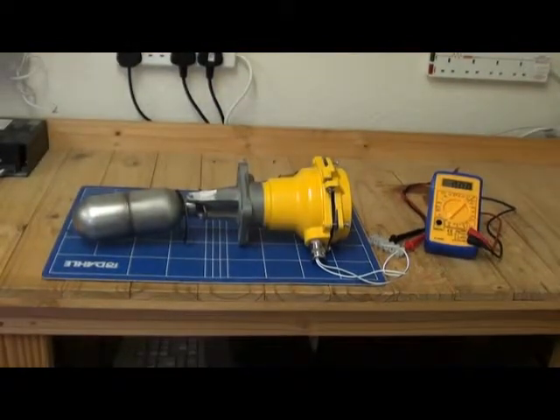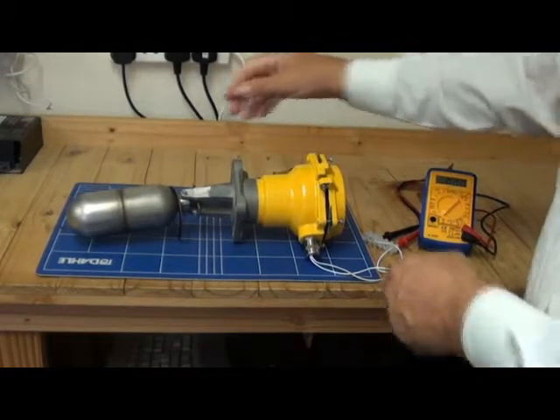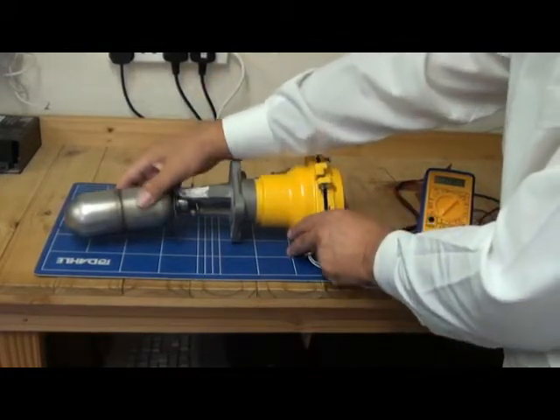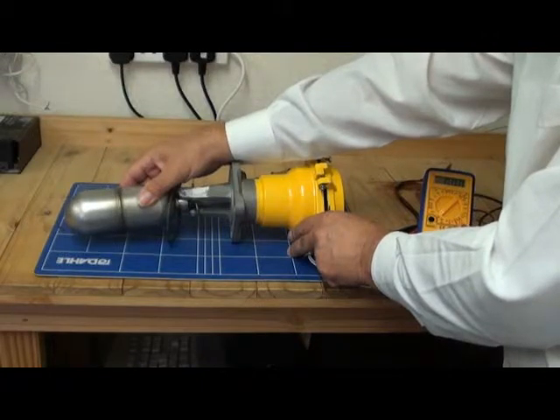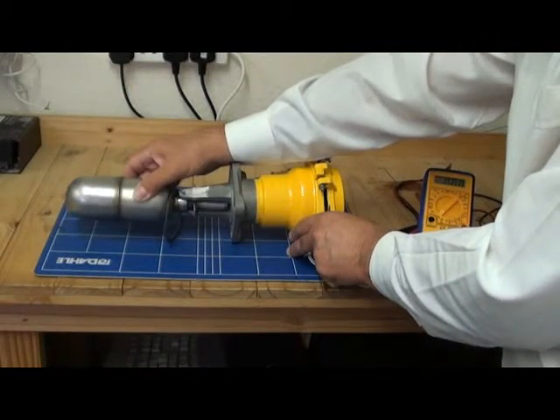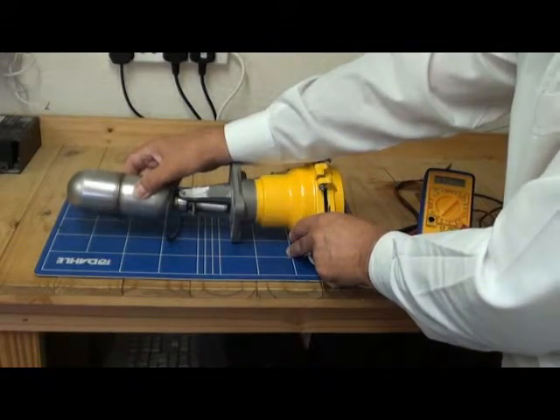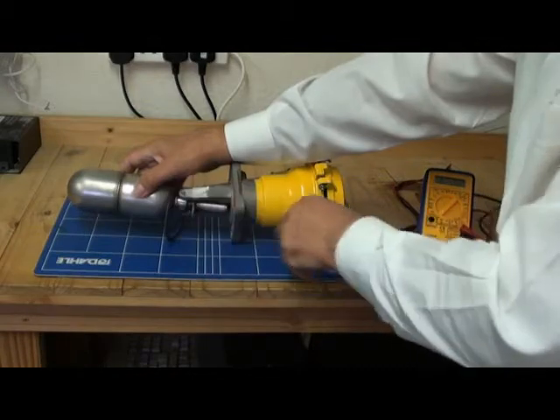If I move the position of the float, so it goes from its low position, if I move it up to simulate a liquid level rising, there you could hear the switch snapping over, the magnets in repulsion snapping over.